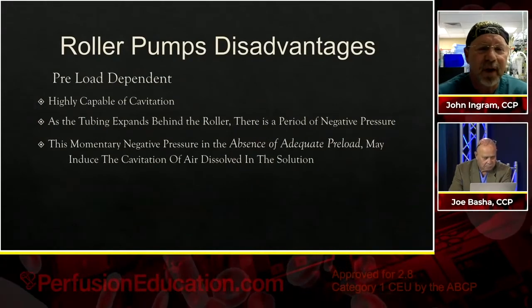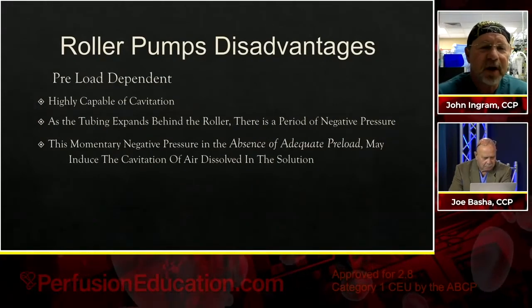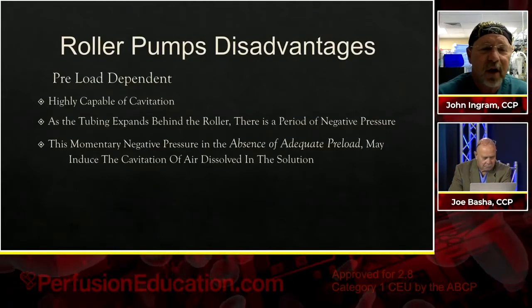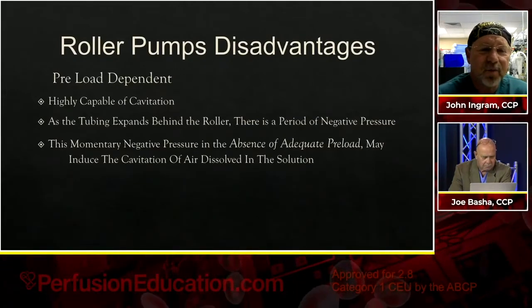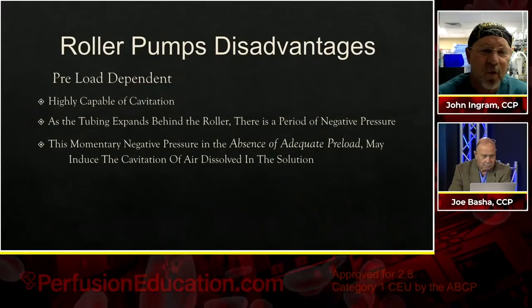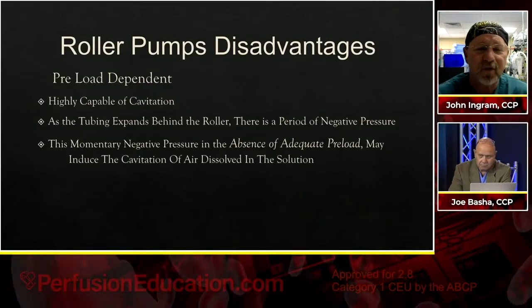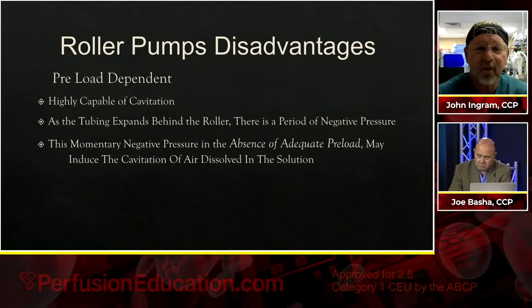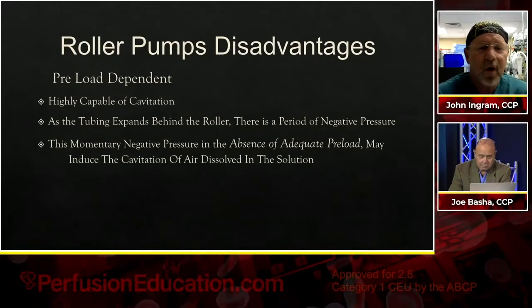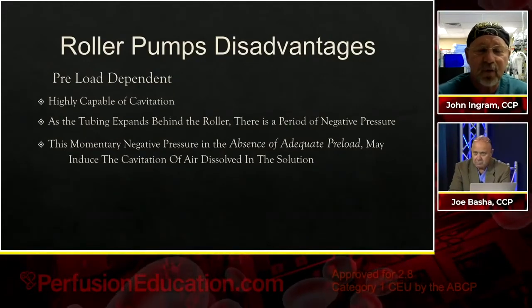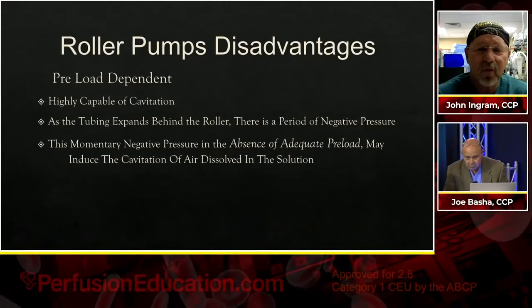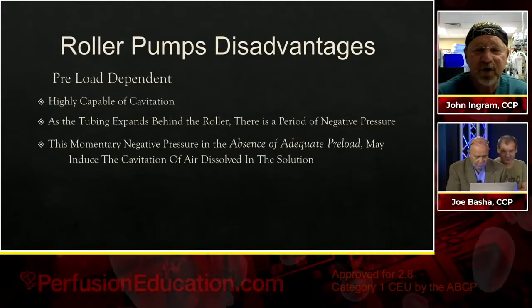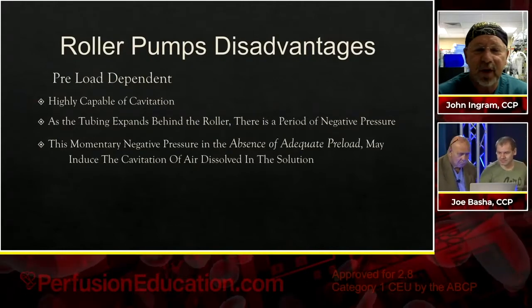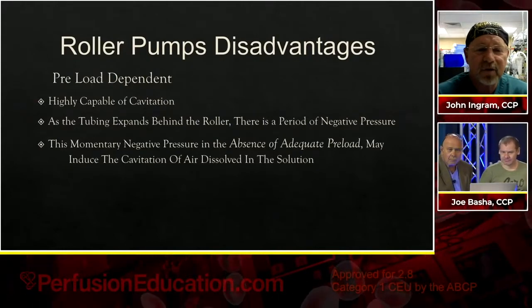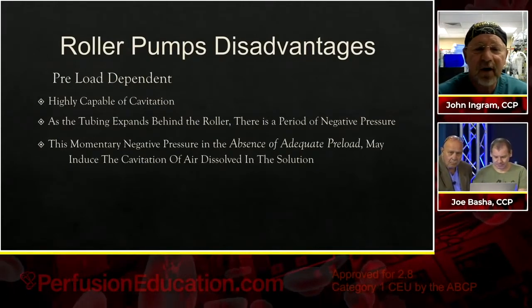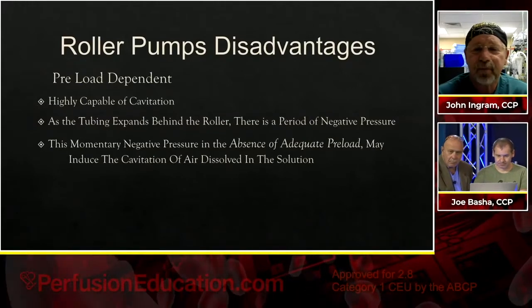There's a preload dependent that's a disadvantage because it's highly capable of cavitation. Now, as the tubing expands behind the roller, as the roller is going through the pump and the tubing is being compressed, there is a period of negative pressure. This is a momentary negative pressure right behind the roller. It's a momentary negative pressure in the absence of adequate preload. And it may induce the cavitation of air dissolved in the solution.